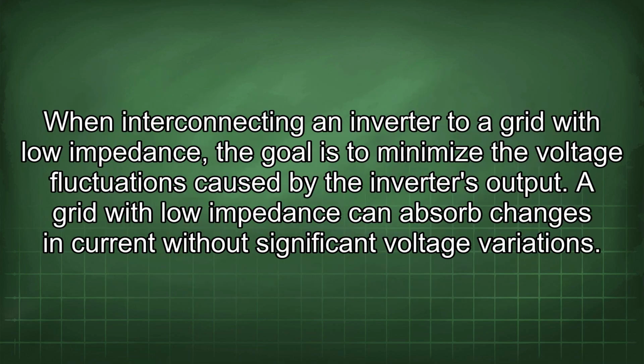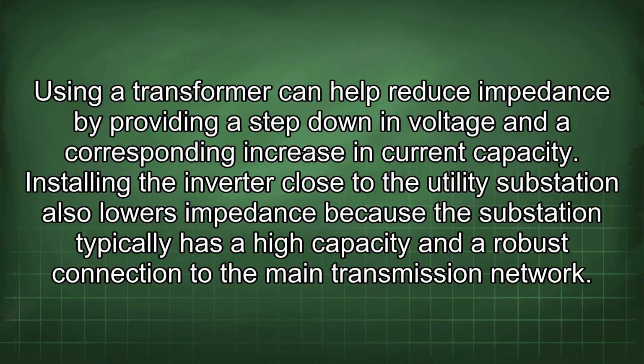When interconnecting an inverter to a grid with low impedance, the goal is to minimize the voltage fluctuations caused by the inverter's output. A grid with low impedance can absorb changes in current without significant voltage variations. Using a transformer can help reduce impedance by providing a step down in voltage and a corresponding increase in current capacity. Installing the inverter close to the utility substation also lowers impedance because the substation typically has a high capacity and a robust connection to the main transmission network.